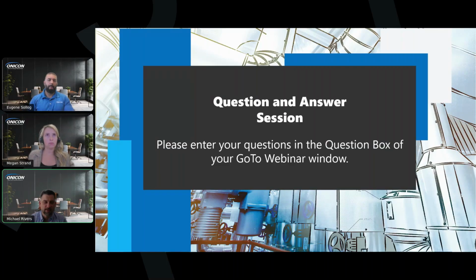You know, I would say when we see this, it's a pretty conservative approach to put a bypass around an inline mag. I think this kind of goes along with how Megan was answering what kind of maintenance is required. And there's no moving parts, like Vince mentioned there. So if anything does fail with the meter, it's typically going to be in the transmitter, which can be replaced in the field. So I would say it's not very common, especially in the larger sizes. Maybe the smaller sizes, it's a little bit more cost effective to put a bypass around it if you want to have a conservative approach.